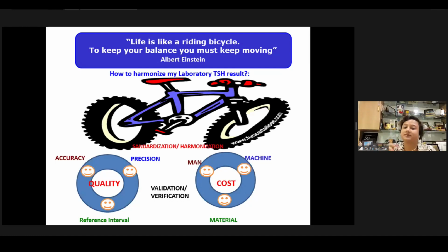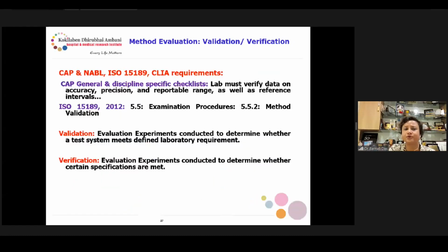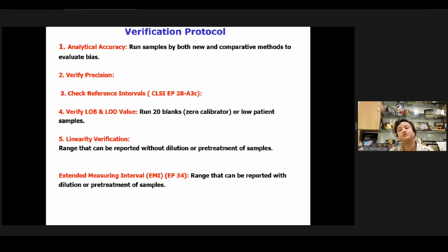This balance will be achieved by harmonization, standardization, and proper IQ, OQ, and PQ. If we do proper IQ, OQ, and PQ, we can harmonize our protocols quite a bit and reduce the variation between methods. Verification and validation play a very significant role, as we know from ISO 15189:2022, and the CAP checklist also mentions that verification and validation are very important.